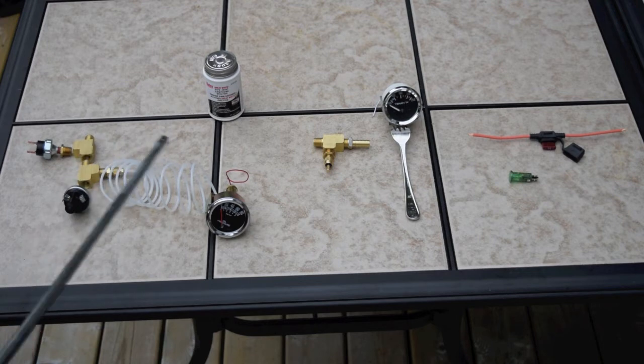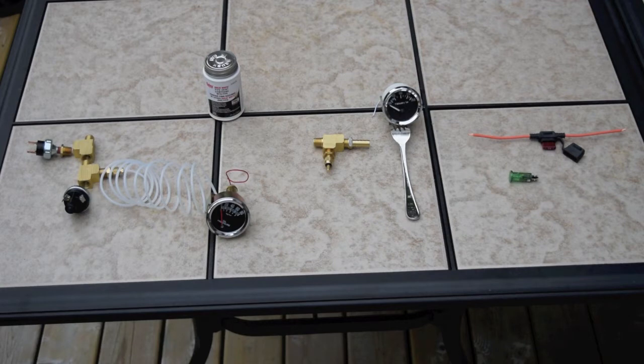There's the pipe dope that I'm going to be using for the threaded connection. It's OD pipe dope. It's for use on PVC, CPVC, ABS, polyethylene, polypropylene, iron, steel, copper, and brass pipes. It's good for water, steam, oil, caustics, and dilute acid. On gases it's good to 3,000 PSI from minus 50 to plus 400 Fahrenheit. On liquids it's good to 10,000 PSI from minus 50 to plus 500 Fahrenheit.